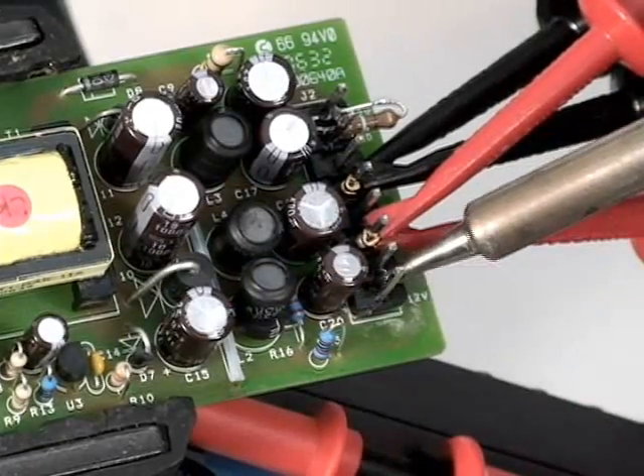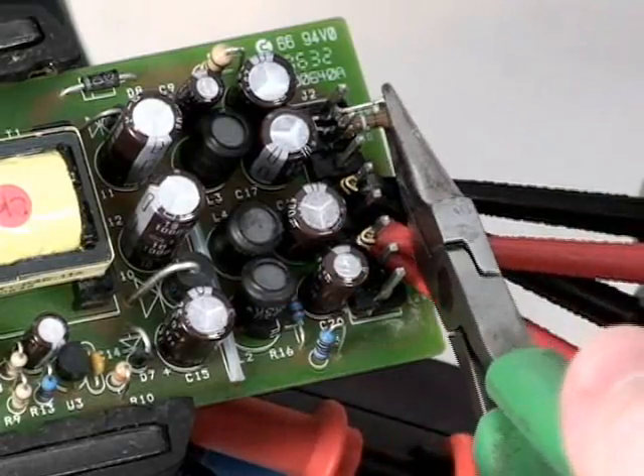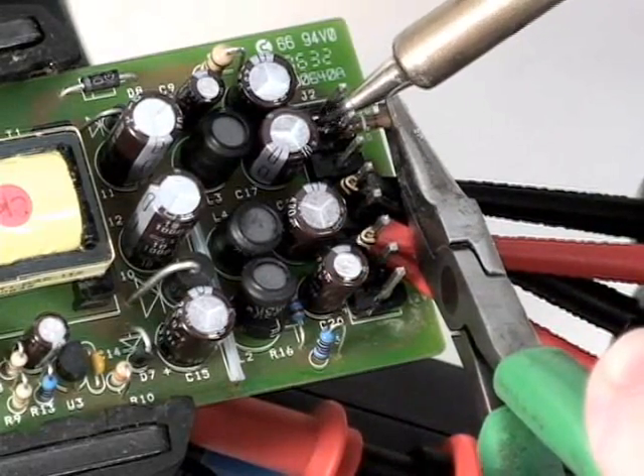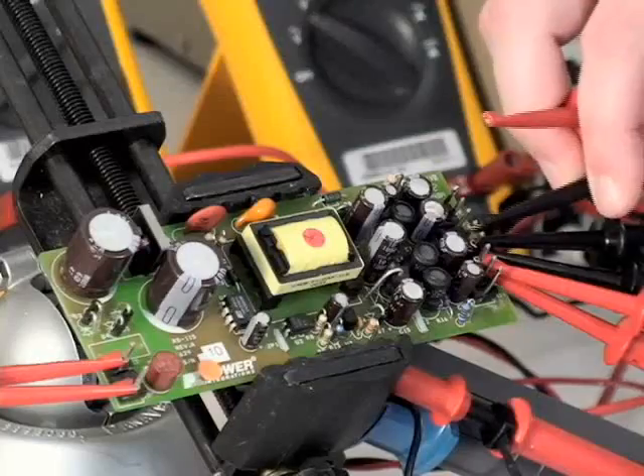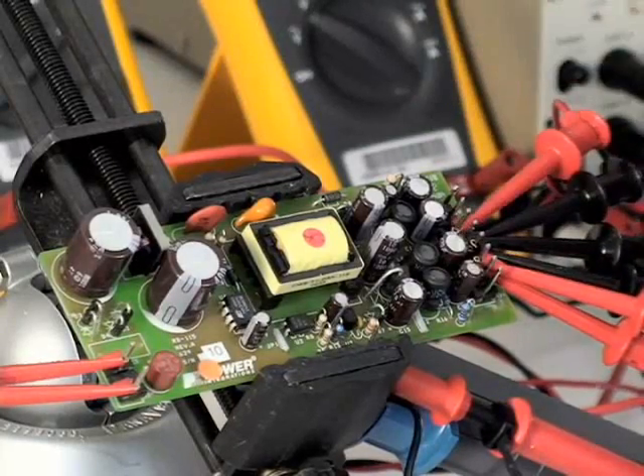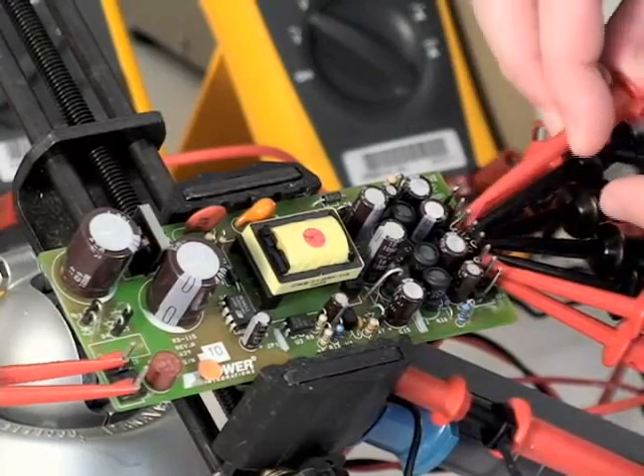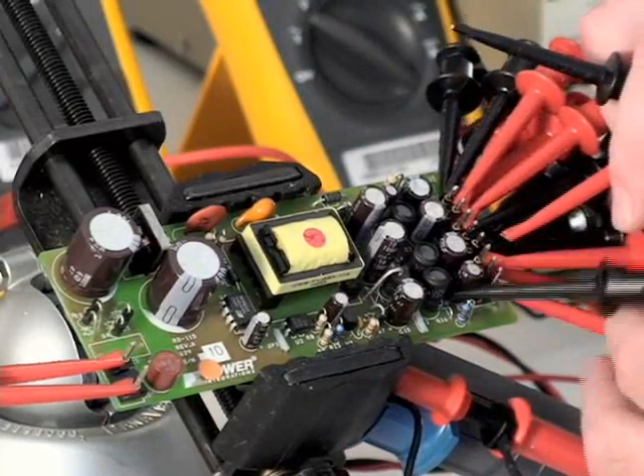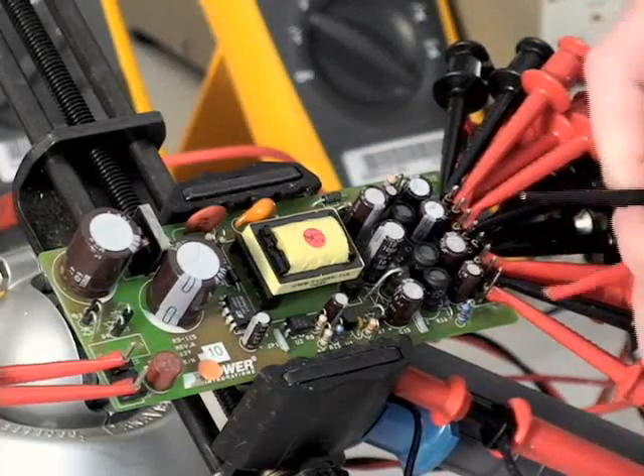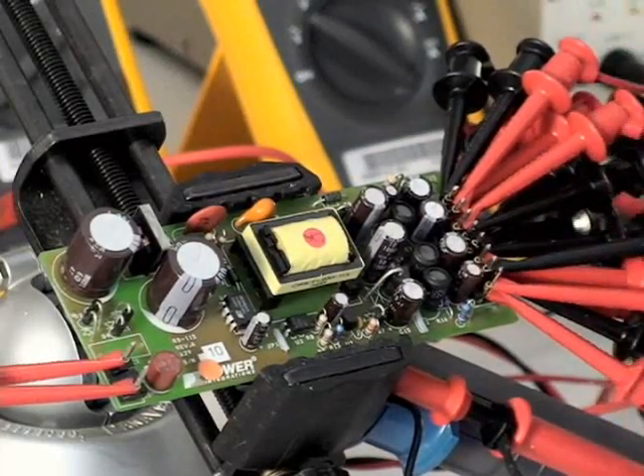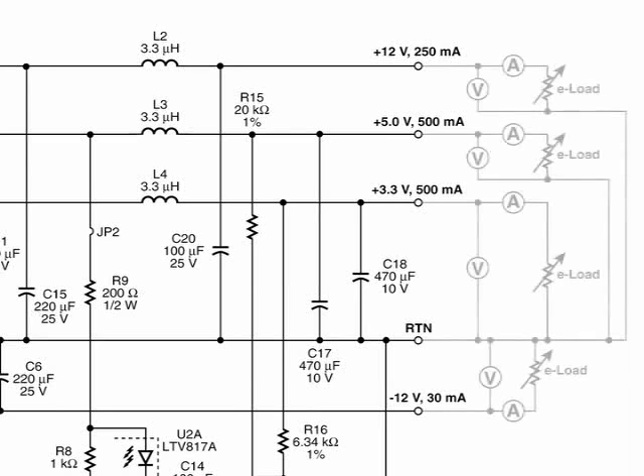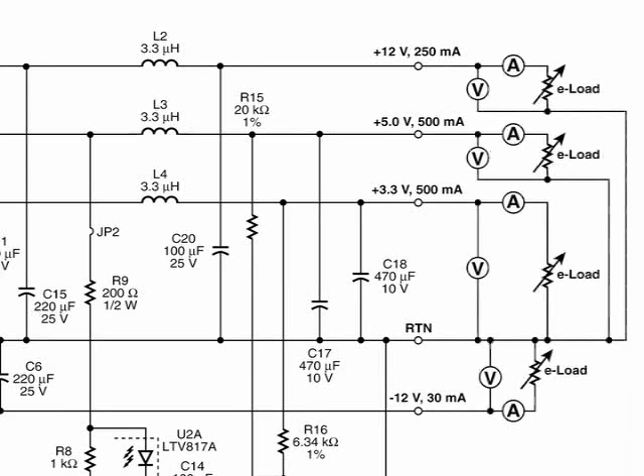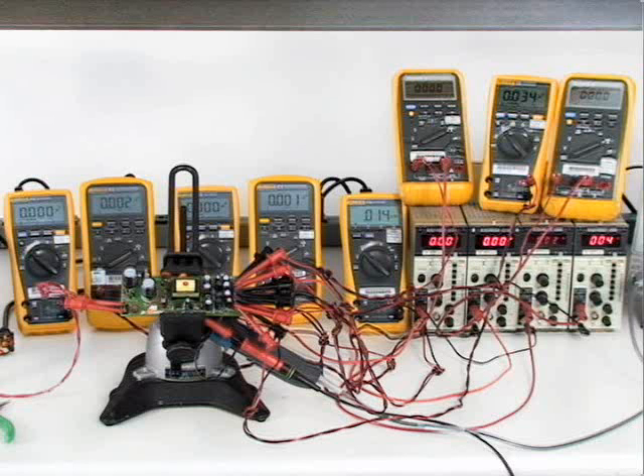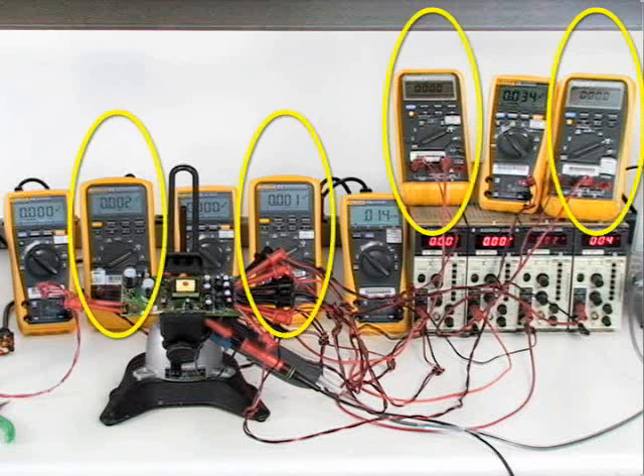If your design includes multiple outputs, turn off the AC input and remove the minimum load resistors you installed earlier. Replace each of these resistors with an electronic load until all outputs of your design are loaded. If electronic loads are not available in your setup, please refer to the introduction course for more loading options and information on how to substitute them. Connect two multimeters to monitor output voltage and current for each output, as demonstrated earlier. For this design, with a total of 4 outputs, this requires a total of 8 multimeters, with at least 4 having a high-resolution current range.